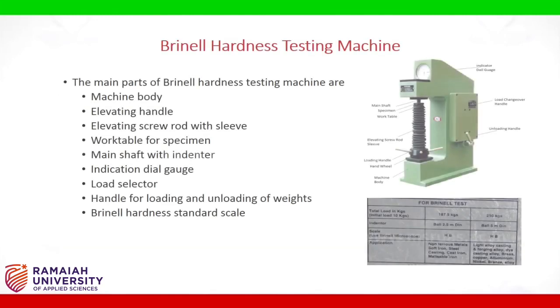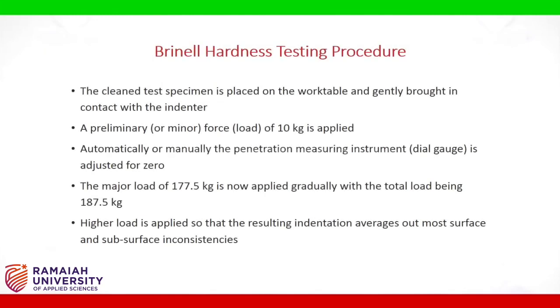The main parts of the Brinell hardness testing machine are the machine body having loads and levers inside, elevating handle, elevating screw rod with sleeve, work table for specimen, main shaft with indenter, indication dial gauge, load selector, handle for loading and unloading of weights, and the Brinell hardness standard scale. The cleaned test specimen is placed on the work table and gently brought in contact with the indenter.